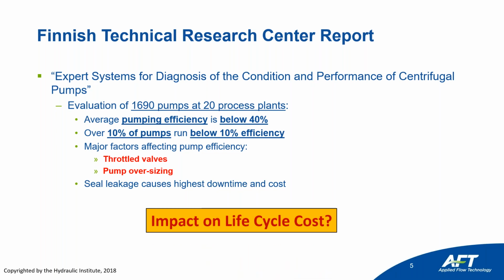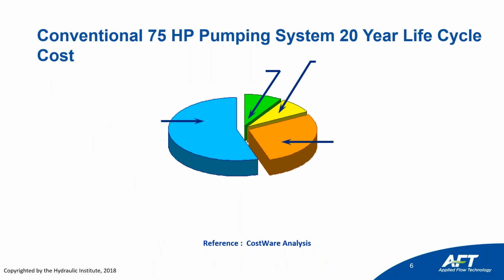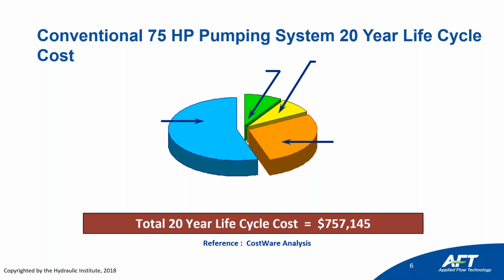So what's the impact of this on life cycle costs? Here's an example for a conventional 75 horsepower pumping system, and we're looking at what the makeup of all the costs are over the 20-year life cycle of that system. And so the total 20-year life cycle cost is $760,000. Okay, well, what makes up that $760,000 over 20 years? 9% is the initial cost, $70,000. That's how much it costs to buy the system, and then you have to install it. Installation is about 8% typically.